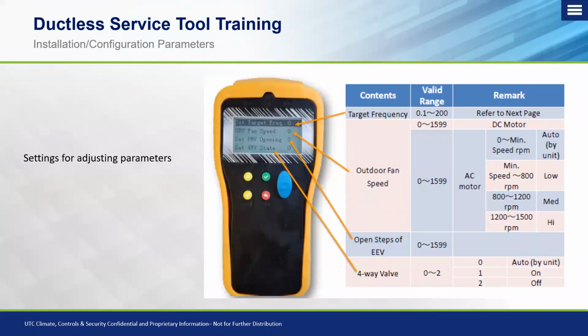So when you're going in the menu that comes with this tool, it'll give you a certain range that is valid, from not running at all to the maximum range that it can run. This is just something you want to pay attention to, especially if you're trying to navigate through here and set different settings. Typically, I don't use this if I'm firing off individual components. I usually just turn them up to a certain degree and let them run. But if you're trying to mimic a certain scenario, whether a fan speed's going out of control or a certain frequency where the compressor seems to have issues or kicks off, this is certainly something you want to have in your possession to know where you can adjust things, what the minimum and what the maximum is.